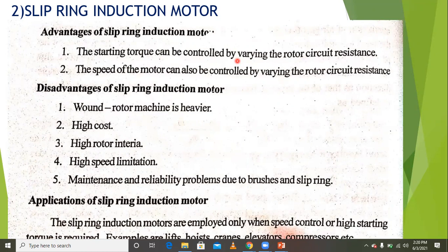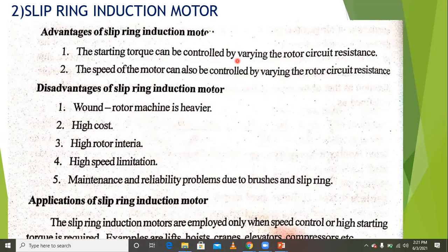In the slip ring induction motor, it is possible to insert resistance into the rotor circuit by using slip rings. External resistance can be connected to the rotor circuit via slip rings, so the starting torque can be controlled by varying the rotor circuit resistance.